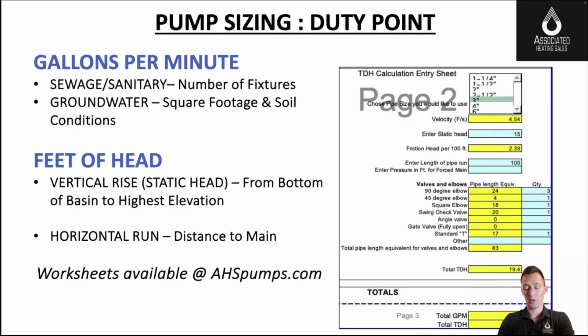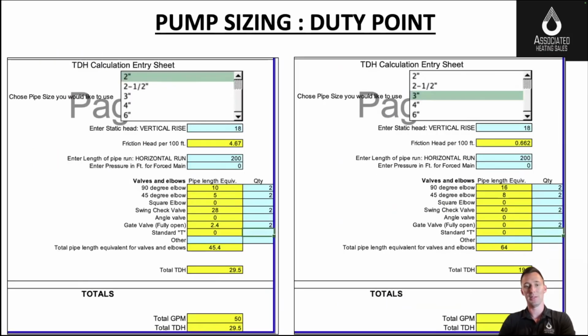If you do 2-inch, it could be quite a bit. So let's just look at an example to illustrate my point there. It was a little confusing, but the vertical, we're going to add then the horizontal. So we know the vertical in this case was 18 feet. So from the pump at the bottom of the pit all the way to our highest pumped point, 18 feet. We're running 200 feet to our main. And if we ran 2-inch pipe, because we have 2-inch pumps maybe in this case, each 100 foot of run is going to add 5 feet of head. So we're actually adding 10 feet of head to the system if we have 2-inch pipe.